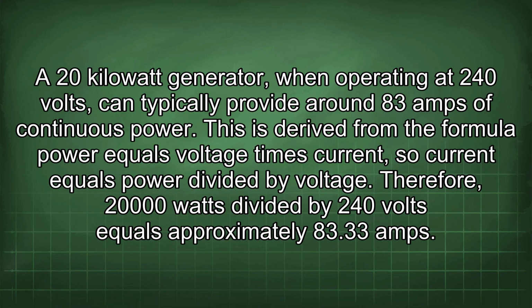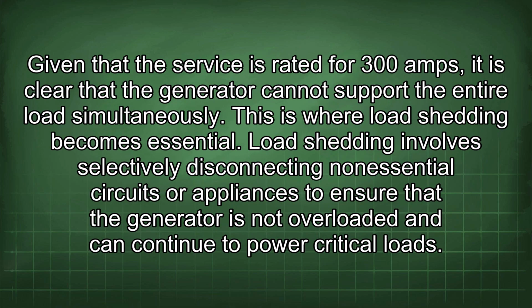A 20 kilowatt generator, when operating at 240 volts, can typically provide around 83 amps of continuous power. This is derived from the formula power equals voltage times current, so current equals power divided by voltage. Therefore, 20,000 watts divided by 240 volts equals approximately 83.33 amps. Given that the service is rated for 300 amps, it is clear that the generator cannot support the entire load simultaneously. This is where load shedding becomes essential.